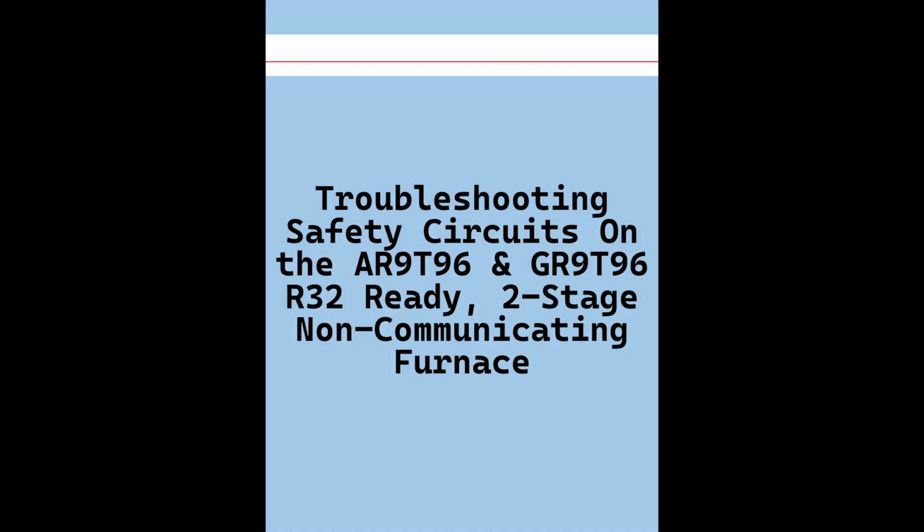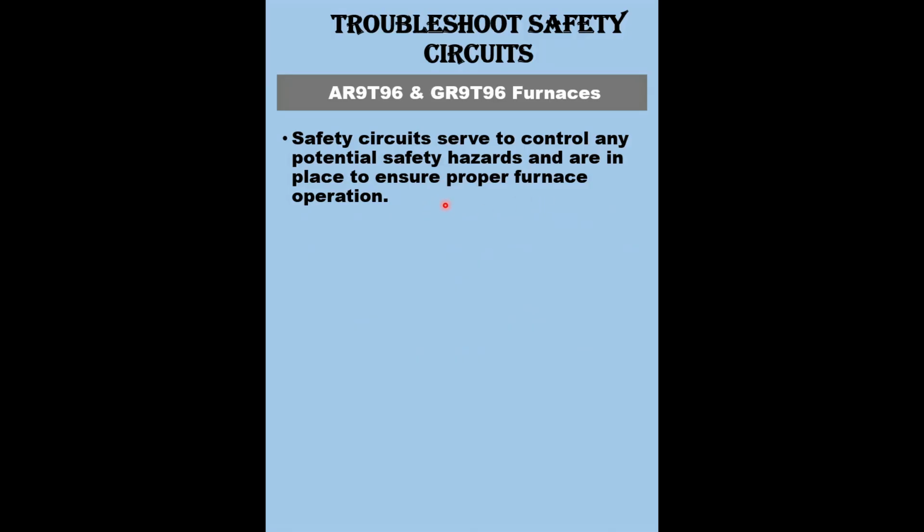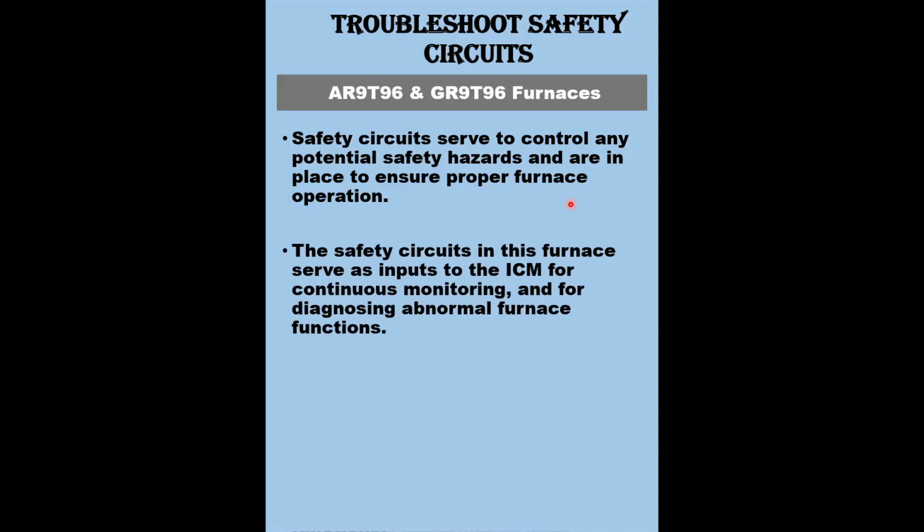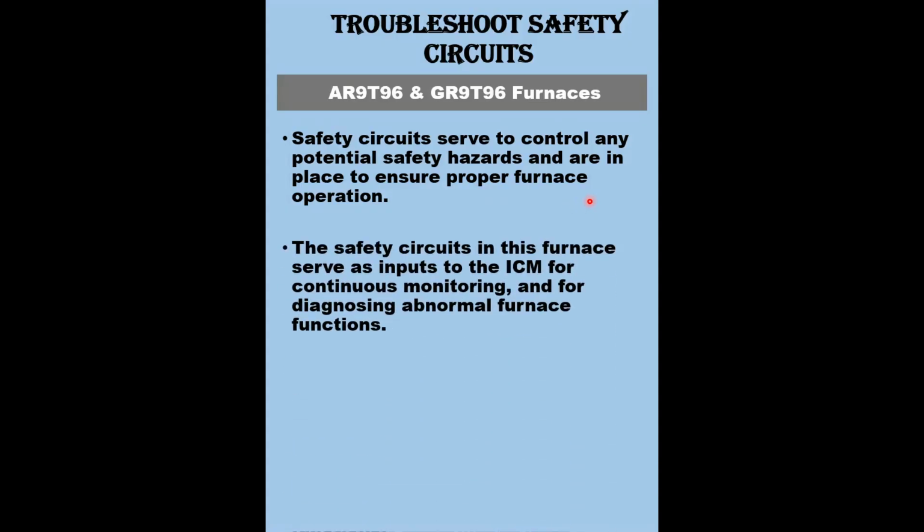GR9T96 R32 ready, two-stage non-communicating furnace. Safety circuits serve to control any potential safety hazards and are in place to ensure proper furnace operation. The safety circuits in this furnace serve as inputs to the control board for continuous monitoring and for diagnosing abnormal furnace functions.